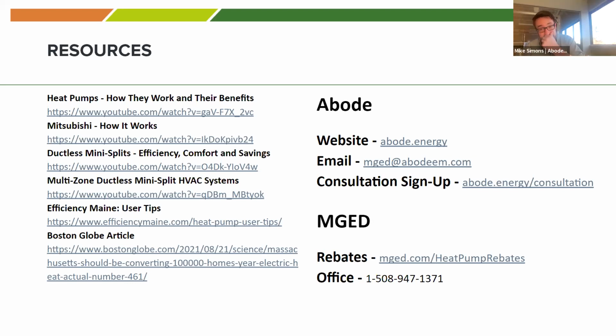It's true for pretty much every high efficiency heating system—any condensing gas furnaces, condensing gas boilers, heat pumps—I'd just plan 15 to 20 years as the useful life. There's certainly equipment that will last longer, and there could be lemons, but the manufacturer's warranty is 12 years. With Mitsubishi it's 12 years, with Fujitsu and LG it's 10 years. So you get a decade of complete peace of mind, but will it last a decade longer than that? As long as you keep it properly serviced—it really is just an appliance at the end of the day. So 15, 20 years.